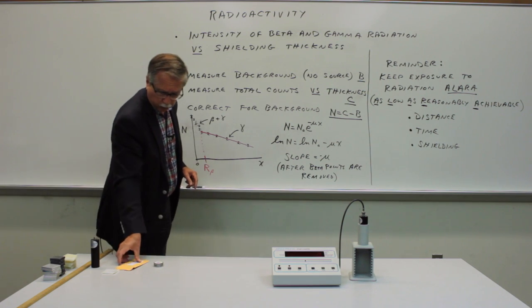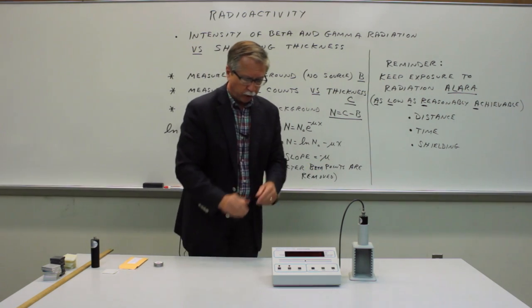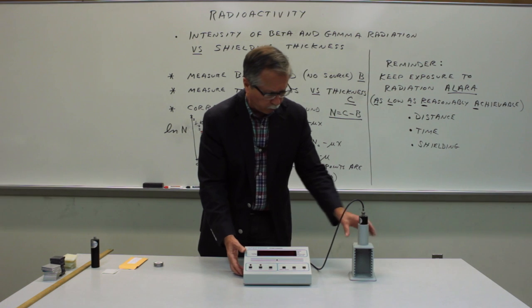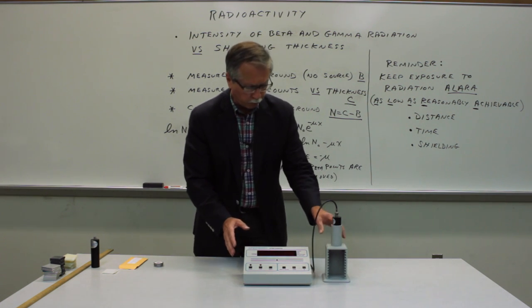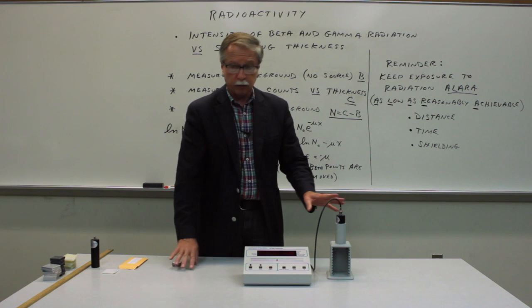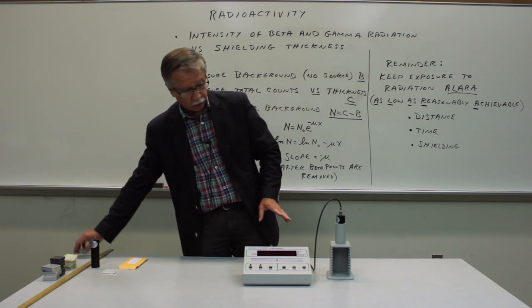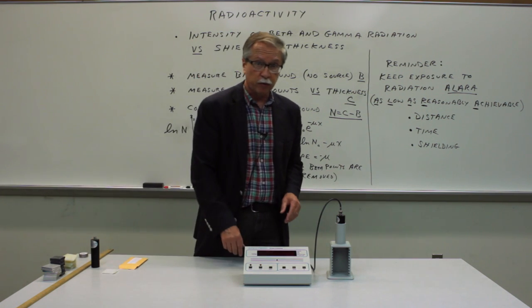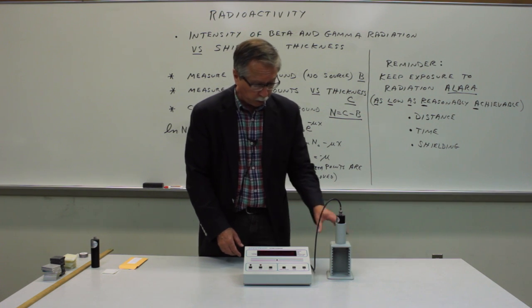So what we need to do is set up the counter as you've done before, set it to the proper operating voltage, and then count the background radiation with no source present. So keep the source far away from the instrument when you're measuring the background radiation.